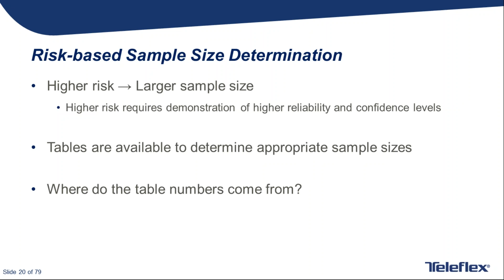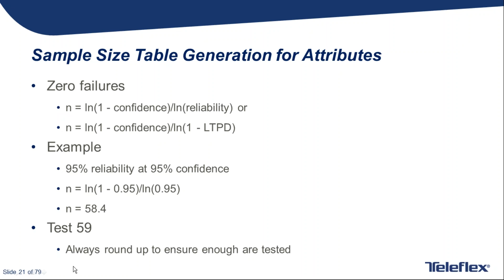First, with attribute testing. Attribute or pass-fail testing is simple. This formula applies to 0 failures. All you need to know is what confidence level is desired and what reliability or lot tolerance % defective is allowed. And then at the end, once the sample size can be calculated from this formula, rounding up all fractional numbers ensures that enough are tested. And we could round up further, and in reality, instead of testing 59 in a case like this, we'd probably test 60 because people are used to using round numbers.